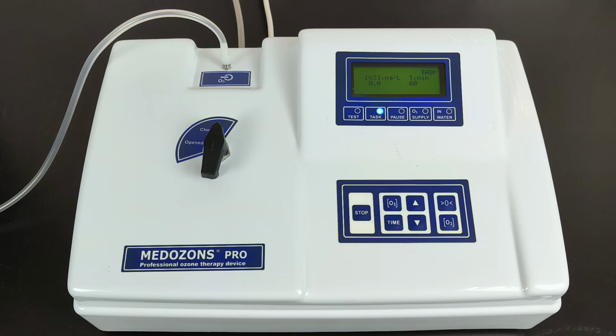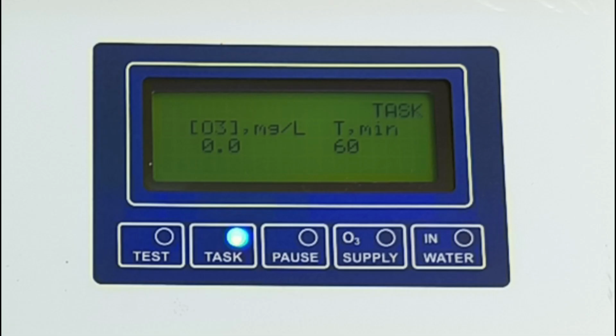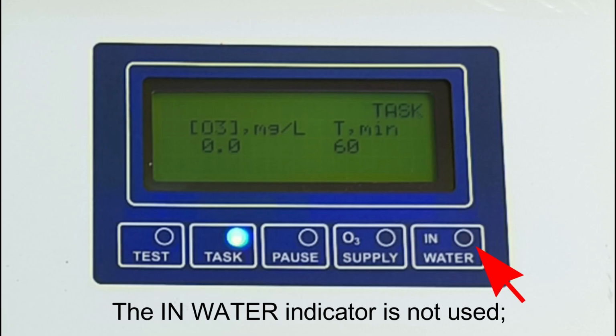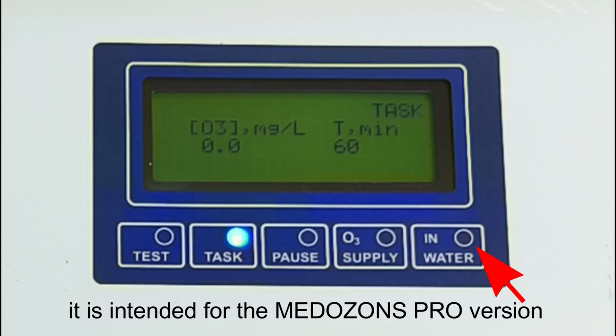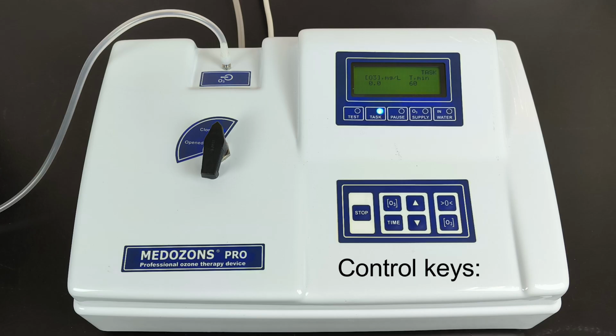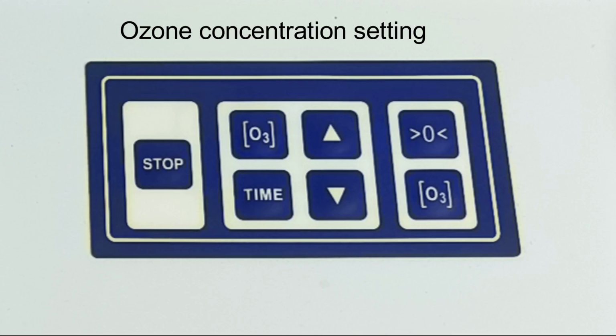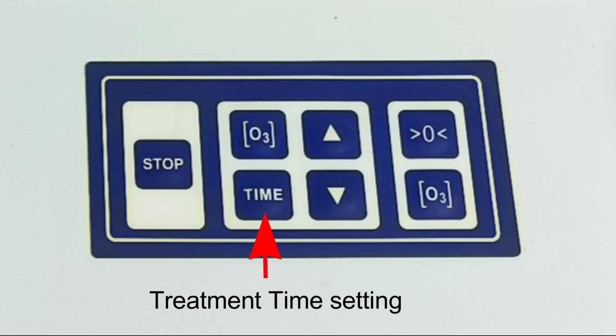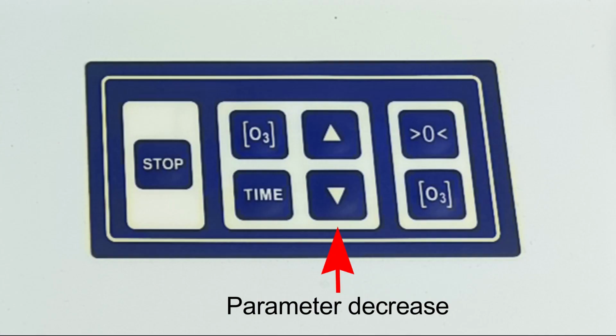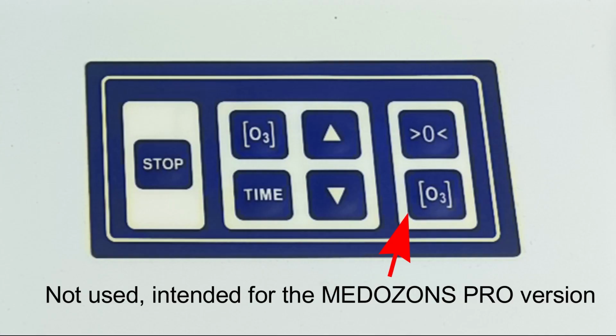Information display. Operating mode indicators: test, task, pause, supply, in water. The in water indicator is not used, it is intended for the Medozons PRO's version. Control keys: Stop. Ozone concentration setting. Treatment time setting. Parameter increase or decrease. One key is not used, intended for the Medozons PRO's version.